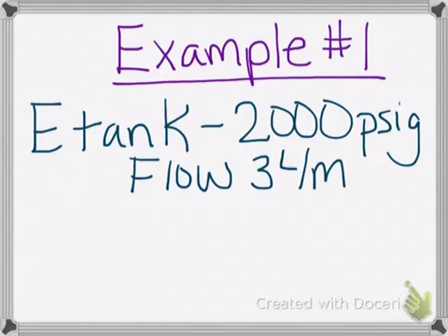Let's do an example. If we have an E tank that has 2,000 PSIG and the patient is receiving a flow of 3 liters per minute, how long will this tank last all the way to empty?